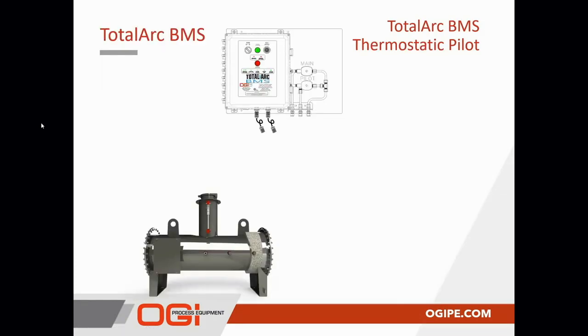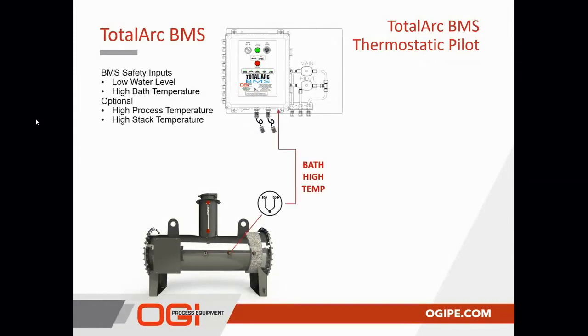In an electronic version of the BMS, all electronic safeties are wired in series into a single safety input. Loss of any of these safeties will cause the BMS lockout and require a local reset. Common heater safety inputs include the low water level switch, the high bath temperature switch, which we've also shown here, an optional high process temperature, and also an optional high stack temperature.